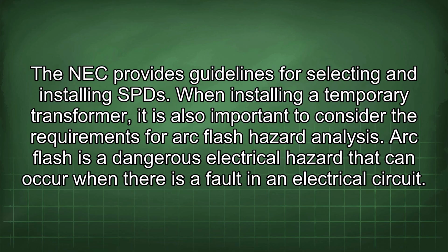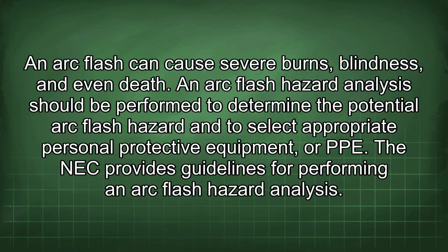When installing a temporary transformer, it is also important to consider the requirements for arc flash hazard analysis. Arc flash is a dangerous electrical hazard that can occur when there is a fault in an electrical circuit. An arc flash can cause severe burns, blindness, and even death. An arc flash hazard analysis should be performed to determine the potential arc flash hazard and to select appropriate personal protective equipment, or PPE. The NEC provides guidelines for performing an arc flash hazard analysis.